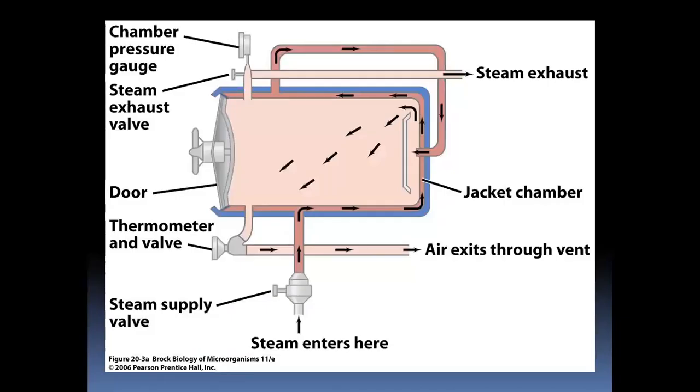This is the autoclave, a picture of a steam autoclave. The functioning of the autoclave is shown. This is the inlet point from where the steam enters, and here is the valve which controls the entry of steam. Either steam is entered abruptly, at high speed or low speed. So this is the valve to control the steam entry.